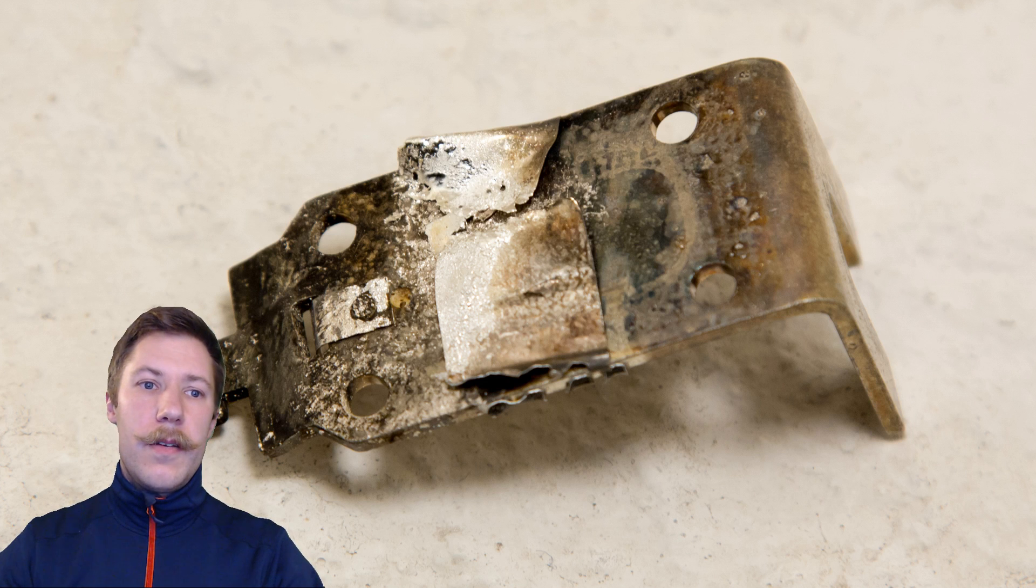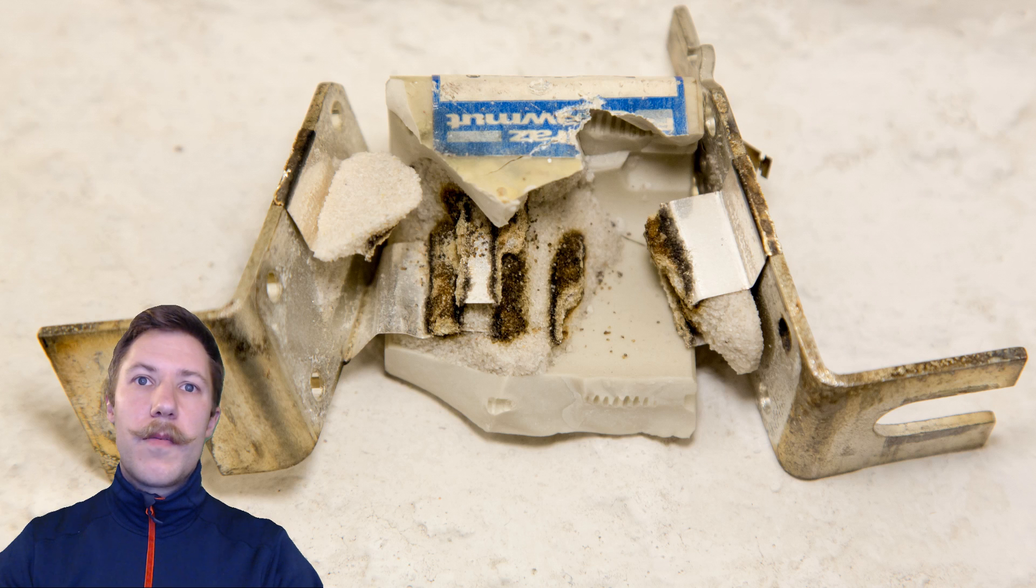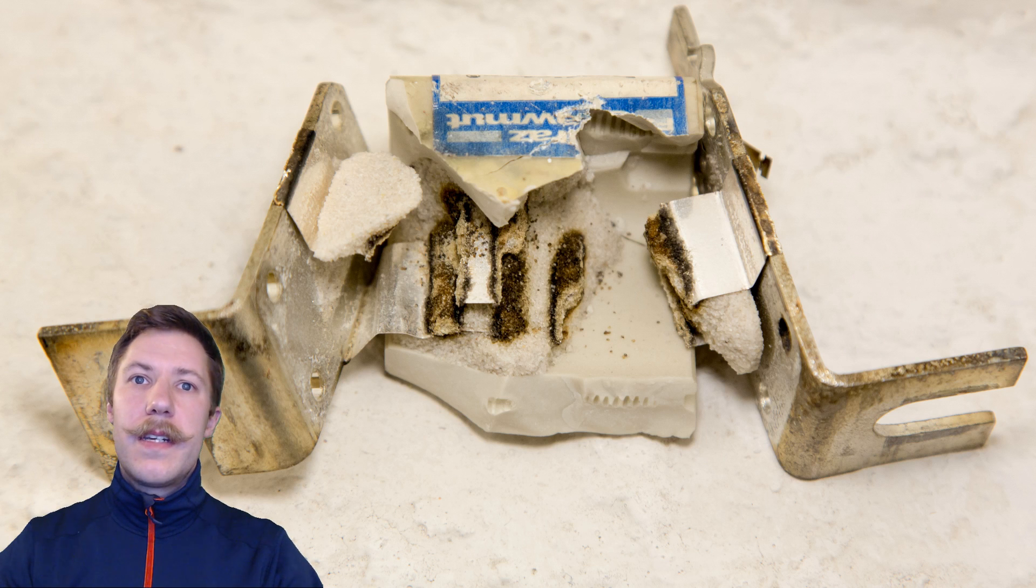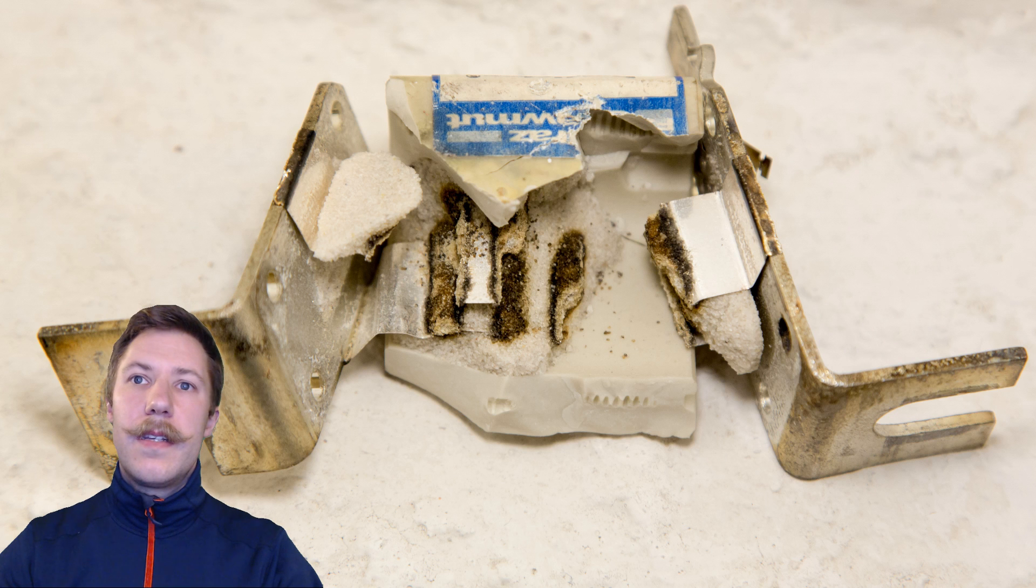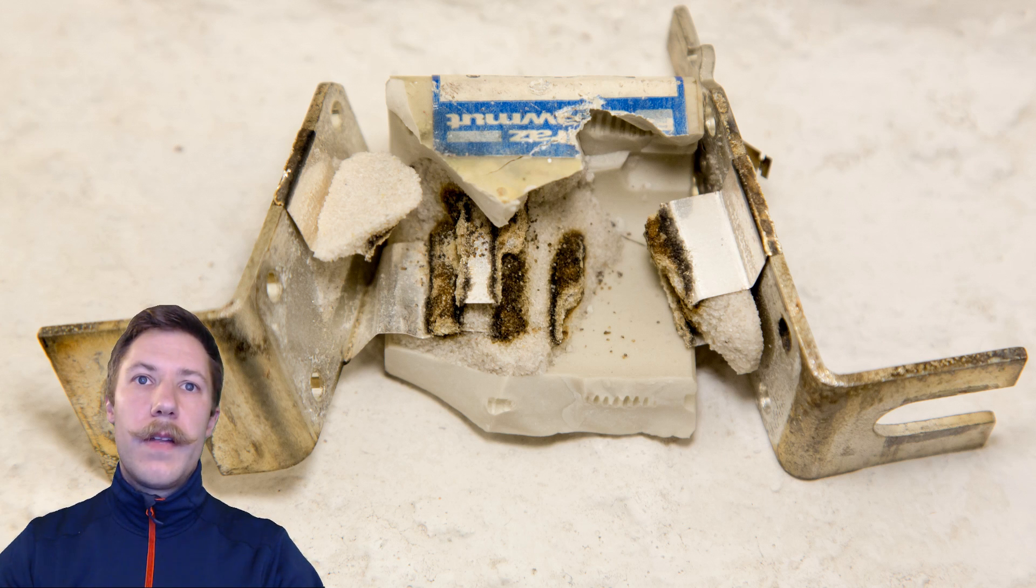It will also isolate the arc from developing further into a larger explosion. Now if we take a look at the fuse that was tested while still in its housing, we can see that the silica sand has melted and it has separated the silver fuse links for the arc to develop any further.